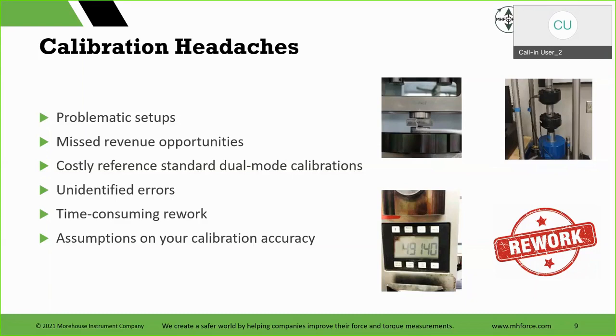A potential customer calls in and says, hey, I need you to calibrate the device and I need you to be four times more accurate. Well, that makes me want to vomit in itself when we're talking about TARs and all of that. We have an article coming out about TAR, it should be RIP, ASAP, but it's still used. So how do you do it? How do you make sure your device is that good? If you're using different fixturing and adapters, we'll talk about all that. So let's talk about those button load cells.